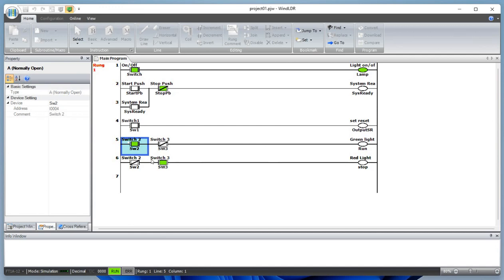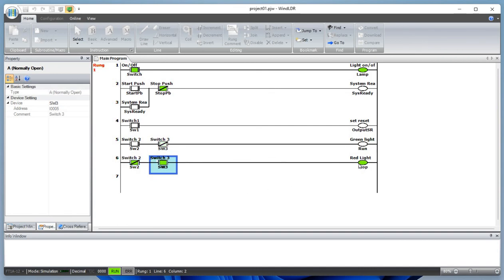Let's simulate. When switch two is pressed and switch three is normally closed, the green light turns on. When switch two is not closed, the green light turns off. When switch three is activated, the red light turns on — but if switch two is toggled, it turns the red light off, putting the system in stop mode. This is how the interlock is done: switch two and switch three use opposite contact types to interlock the output circuit.